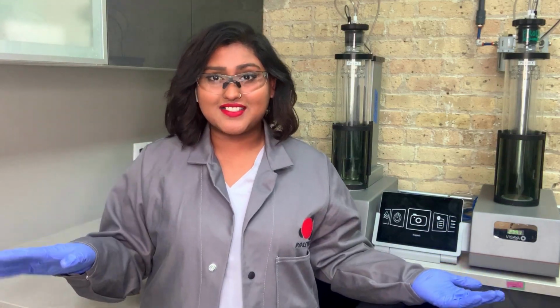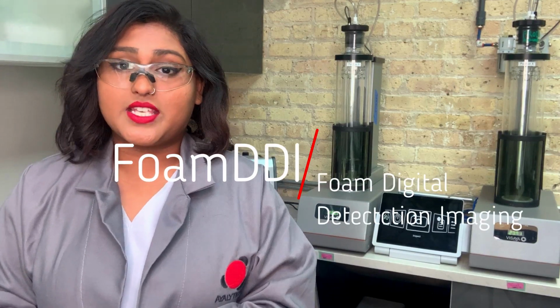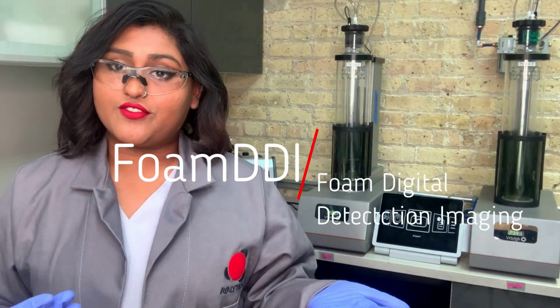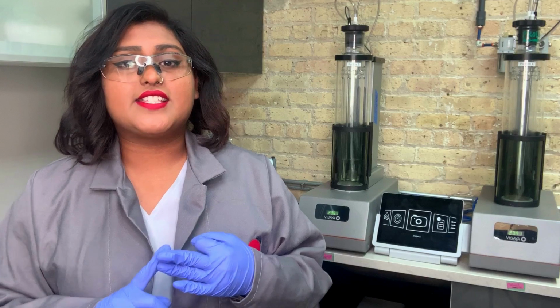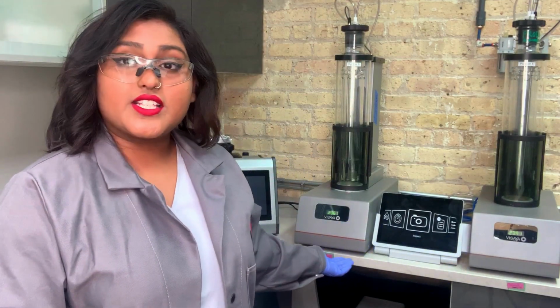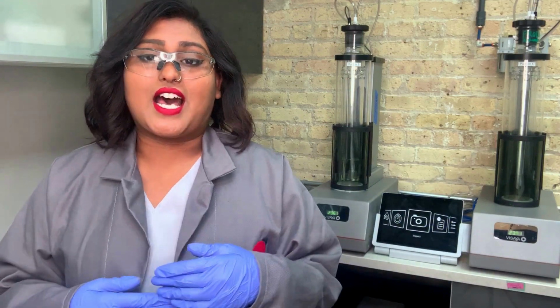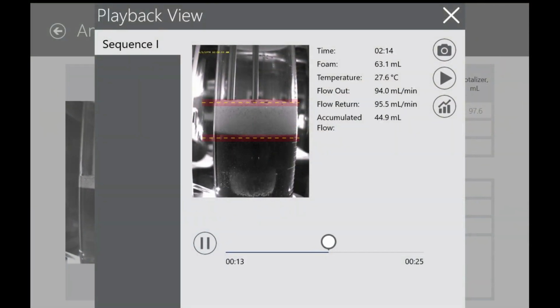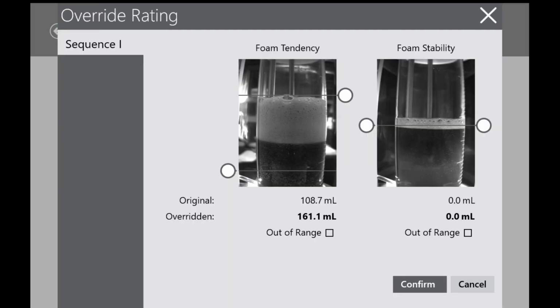You can start the test and just walk away. The FoamDDI, or foam digital detection imaging, accurately controls the airflow, temperature, and time to meet the conditions of each sequence. Each rig is also equipped with a high-resolution camera which records the whole test. The software is able to detect and capture the foam, and the results are saved in both PDF and a video, so you can always go back and watch the test in case of any questionable results.